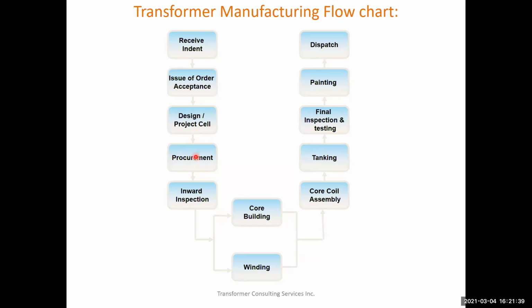The manufacturer will procure the material. Once procured, it starts to show up in the manufacturing factory, where they do inward inspection to control quality. Once the material has been inspected, it is split into two sections - some moves to the core building area, some to the winding area. The conductor insulation package moves into the winding area, while the core steel moves into the core building area.